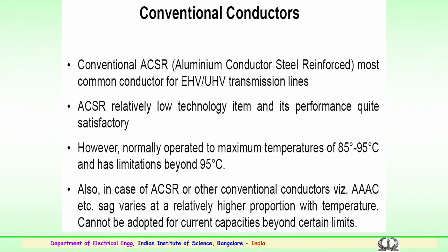However, normally ACSR conductors are operated at a maximum temperature between 85 to 90 degrees, and they have limitations beyond 95 degrees.